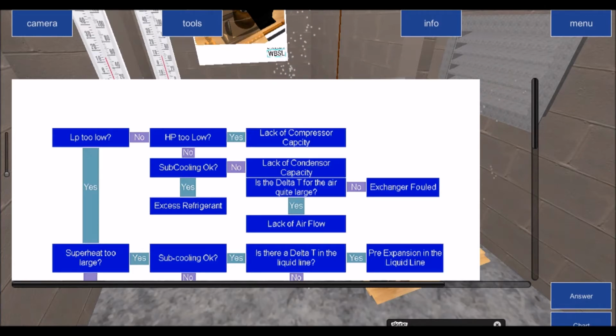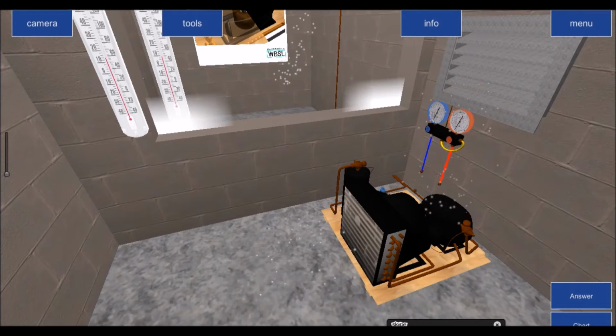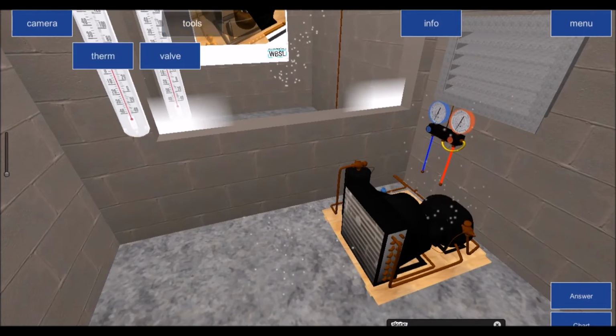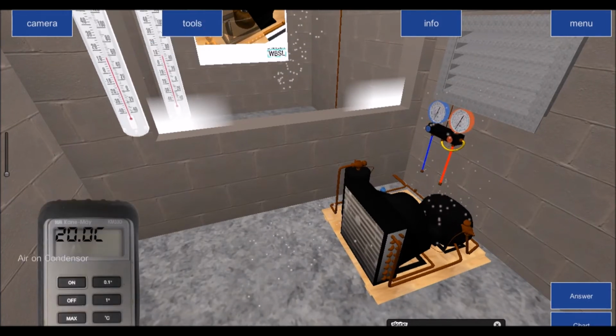So the next thing we need to figure out is, is the delta T for the air quite large? It's a yes or no. So let's have a look. Delta T for the air means the difference between the air on, which is 20 degrees, and the air off, which should be between 5 and 10 degrees of a difference. So if I have air on of 20 degrees, I'm expecting an air off of 25 degrees minimum, and maximum of 30 degrees. So anywhere between 25 and 30.